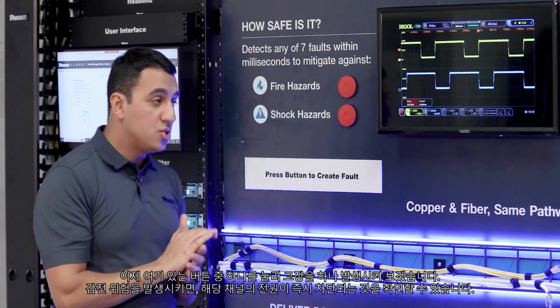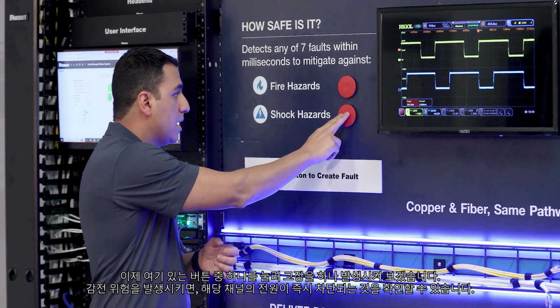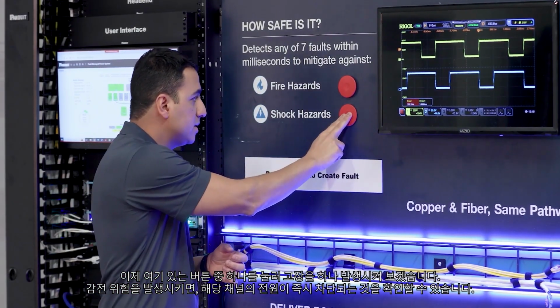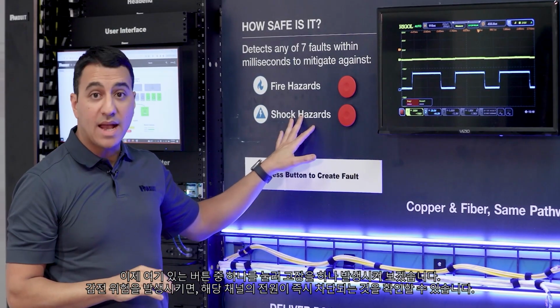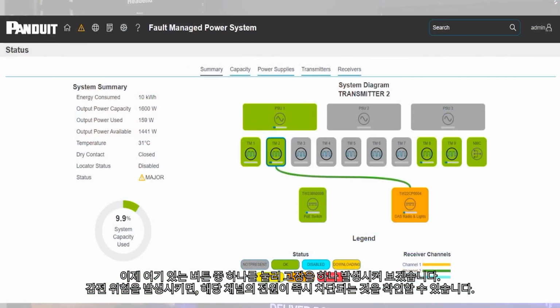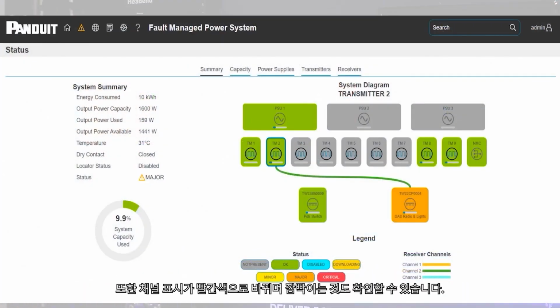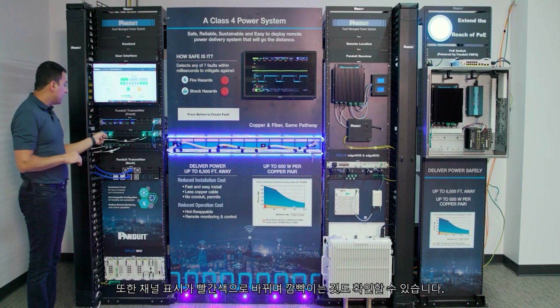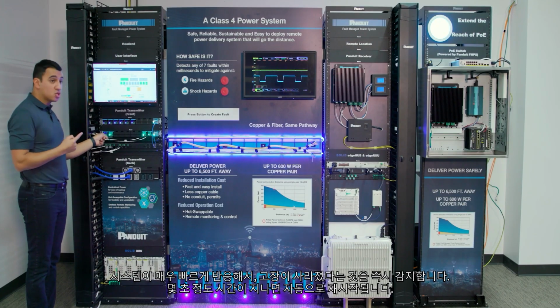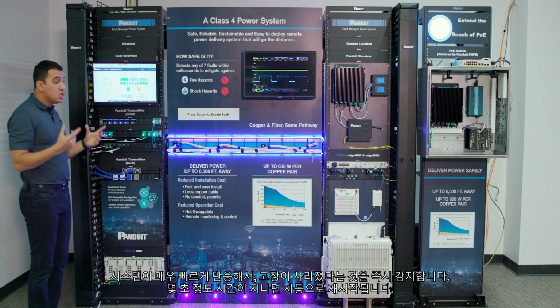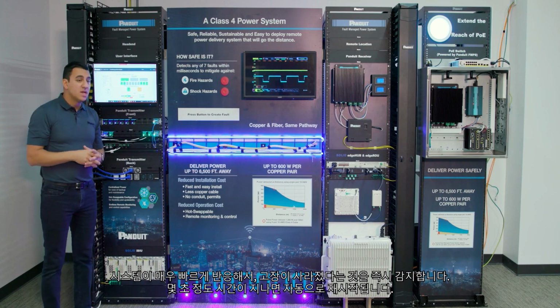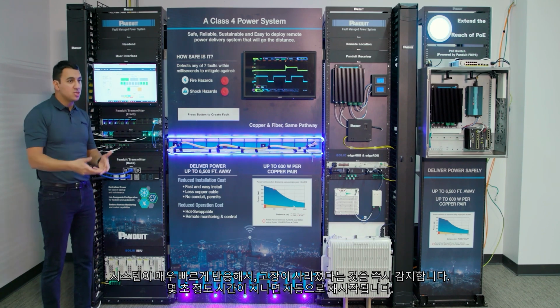So now I'm going to introduce one of the faults by simply hitting one of these buttons, introduce the shock hazard. You can see instantly that channel turned off. You can also see that it went red and it blinked red here. It did it so quickly. It knows that that fault is not there anymore. It takes a few seconds and it will just restart itself automatically.